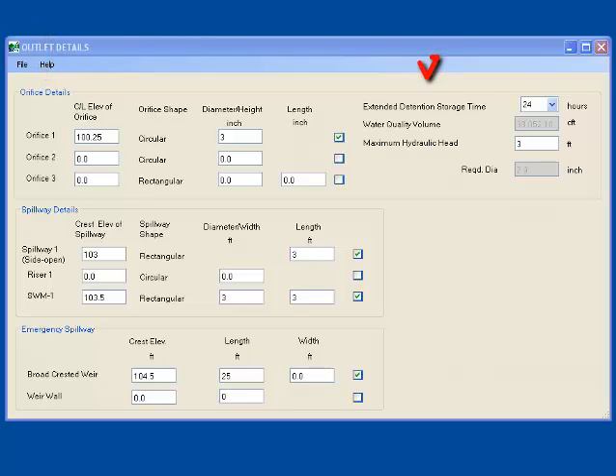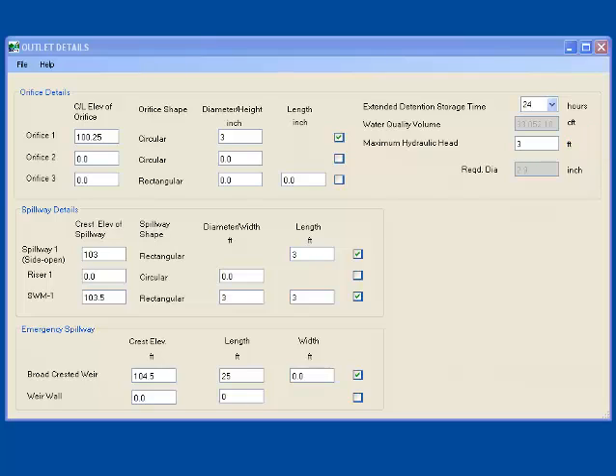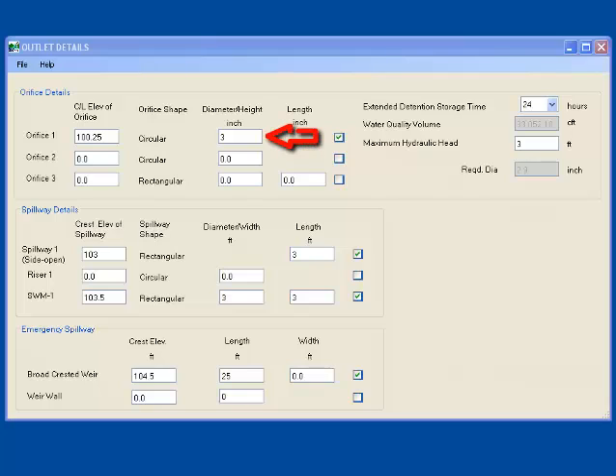To the right, you will notice that the water quality volume required is already populated. I select 24 hours from the pull-down list for extended detention storage time for level 1 design. I enter the maximum hydraulic head. There are two procedures to determine the orifice size to hold the extended detention storage volume. The program uses the DCR method 2 or the average hydraulic head method, which is also the preferred method given in the Virginia Stormwater Management Handbook. This gives the size of orifice in inches. This size is used in the orifice sizing to the left of this form.